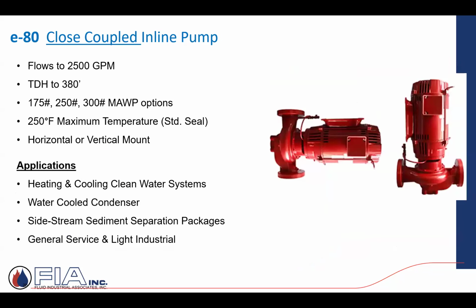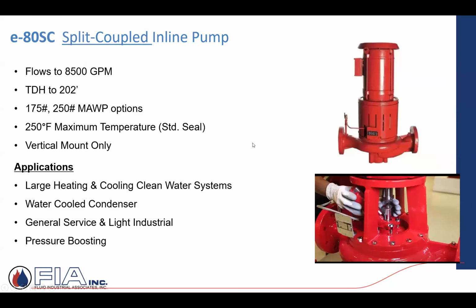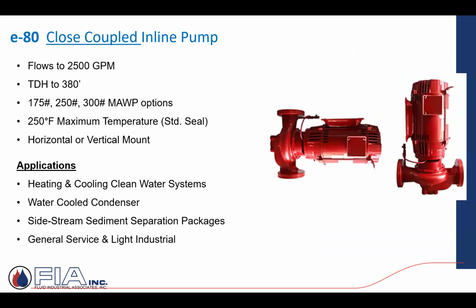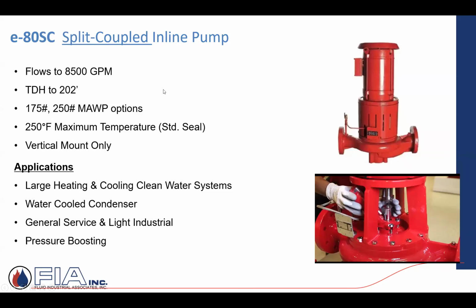And then the E80s, close coupled, same thing, close coupled up to a certain capacity, vertical top to bottom, bottom to top, and same thing left to right. And some of these as well can be oriented both horizontal or vertical. The split coupled is just that larger capacity. If you look at the flows, I mean, it's kind of crazy. I don't know how often we actually see that out in the field. But you go from a close coupled, still pretty substantial flow rate, but all of a sudden you get to this split coupled. It's got some serious capacity, which means some serious horsepower sitting on top of it.